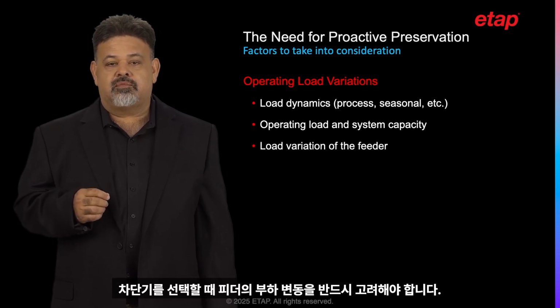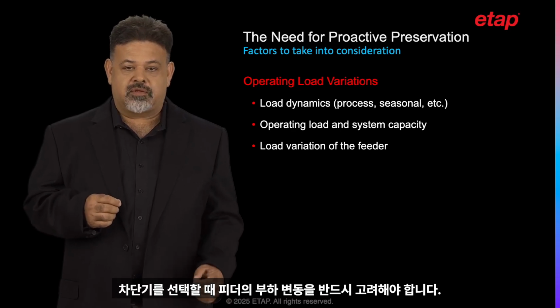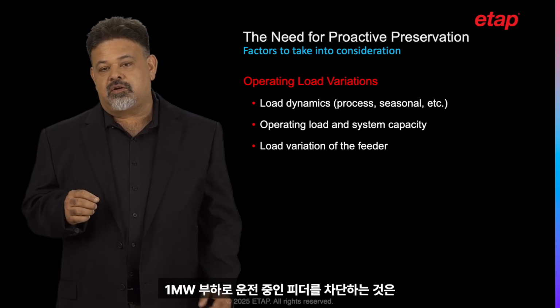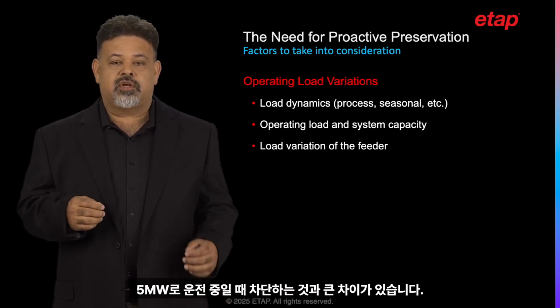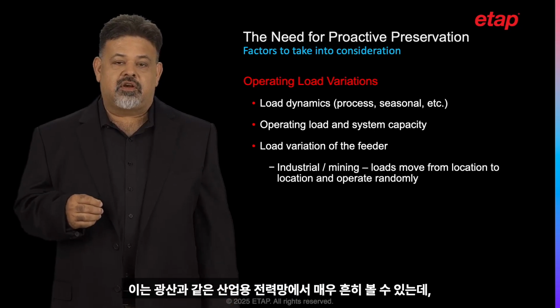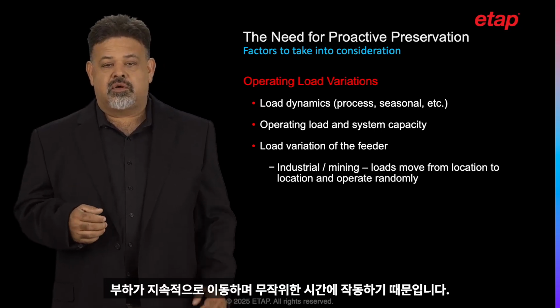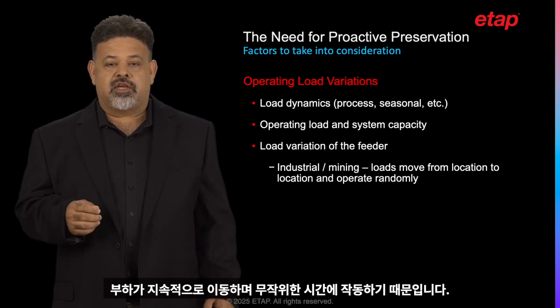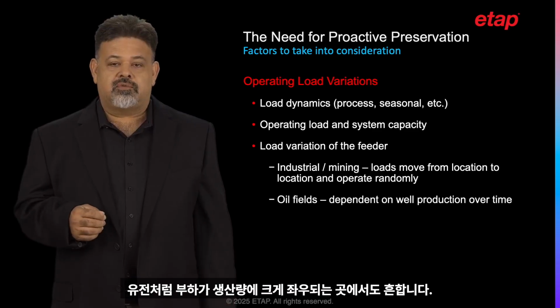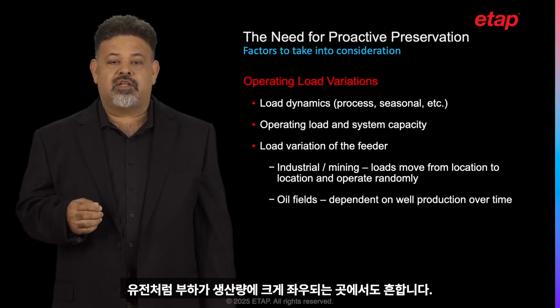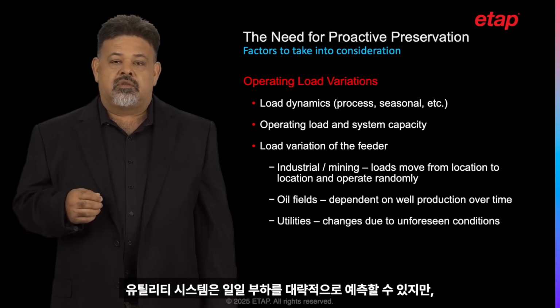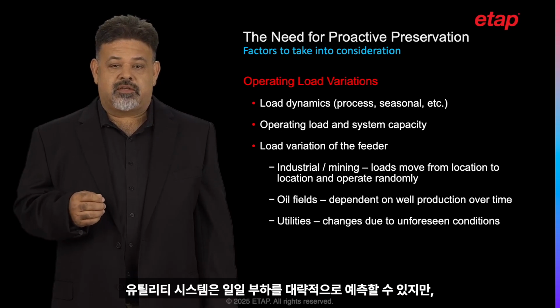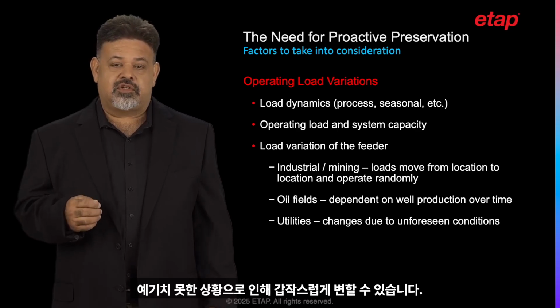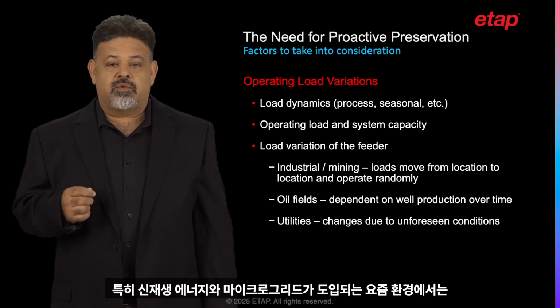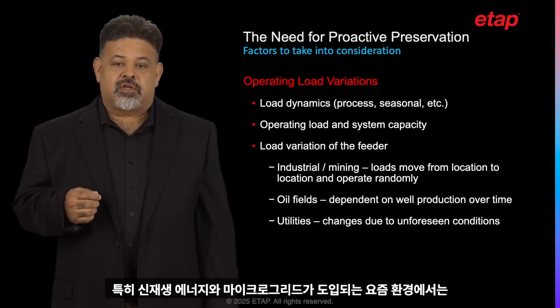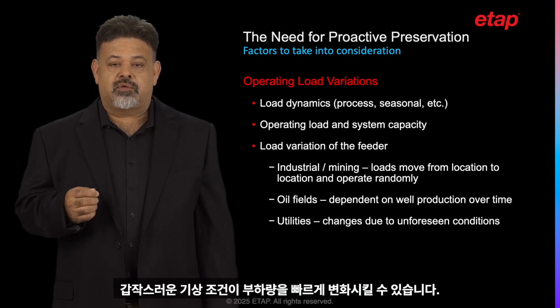Load variation of feeders must be considered when a breaker is selected for tripping. It makes a big difference to drop a feeder operating at 1 megawatt of load compared to when it is operating at 5 megawatts. This is very common in industrial networks, such as mines, where loads constantly move from location to location and can operate at random times, or in oil fields, where the loads depend greatly on the production of the well at that time. In utility systems, although load can be roughly predictable in a given day, it can suddenly change to unforeseen conditions, especially nowadays, where renewables and microgrids are being introduced, and when sudden weather conditions can change loading quickly.